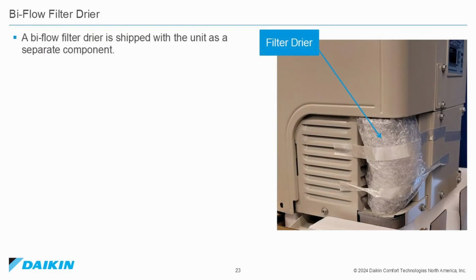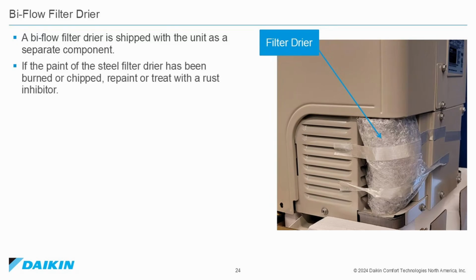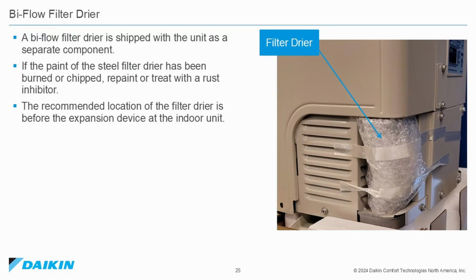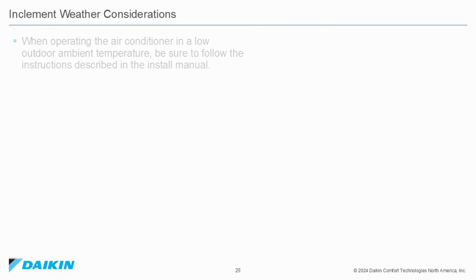Biflow filter dryer. A biflow filter dryer is shipped with a unit as a separate component. If the paint of the steel filter dryer has been burned or chipped, repaint or treat it with a rust inhibitor. The recommended location for the filter dryer is before the expansion device at the indoor unit. Inclement weather conditions. When operating the air conditioner in a low outdoor ambient temperature, be sure to follow the instructions described in the installation manual.